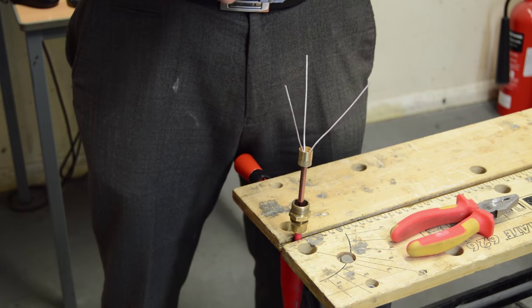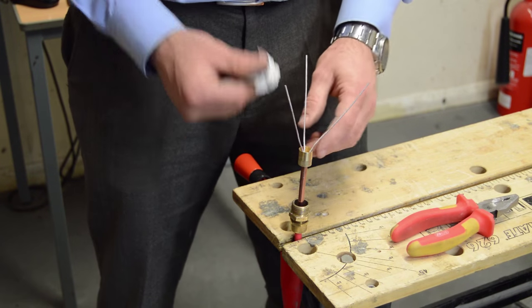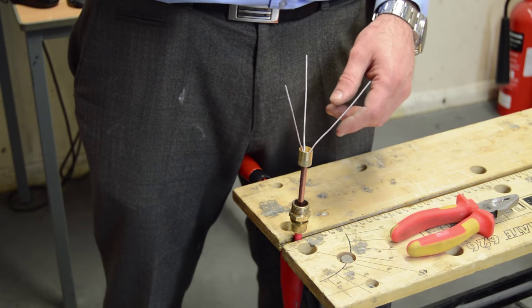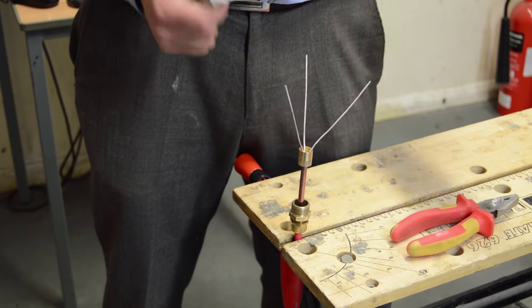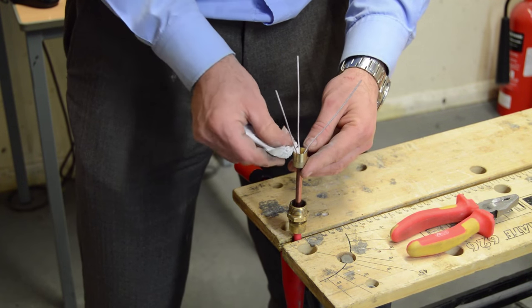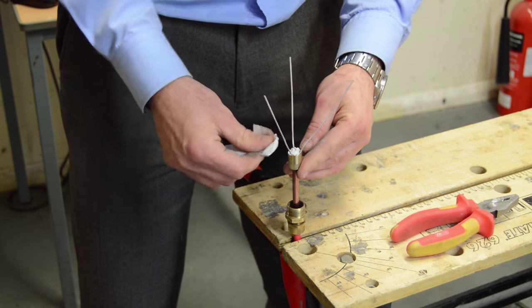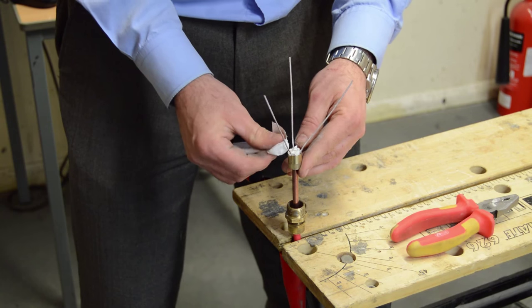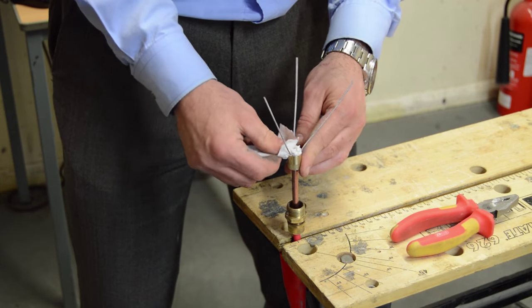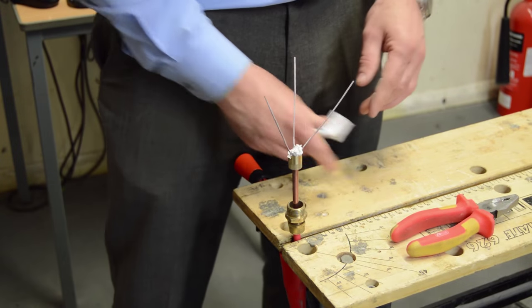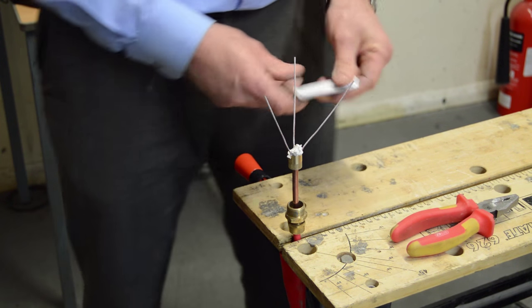So what we're going to do, get your compound. You've got to make sure the compound, because that will just take the moisture out of your fingers and then the magnesium oxide. And you've also got to fill the pot from one side, one side only. The reason behind that, if you fill it from one side the compound will go down and out the other side pushing the air out. So that's what we're going to do now. We're just going to gradually fill the pot. There's no rush, I just want to make sure we get it all in. Yep, plenty of compound in. Once you're finished seal up the compound and keep it ready for your next job.